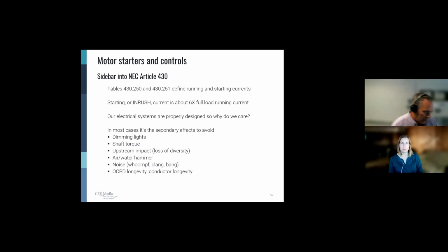We have an upstream impact. And what I mean by that is a loss of diversity. If all of our motors have huge inrush currents, eventually those motors tie back into a particular electrical service, which would have to be sized or upsized accordingly. We can get things like air and water hammer. If that motor stops and starts quickly, we get noises, you know, from our air systems, from our water systems. And then we have to concern ourselves with overcurrent protection device longevity and conductor longevity. Again, if we're shoving a lot of current through these things very fast, L di/dt, as you recall, we're going to stress these things as opposed to us providing current at a slower, steadier pace.